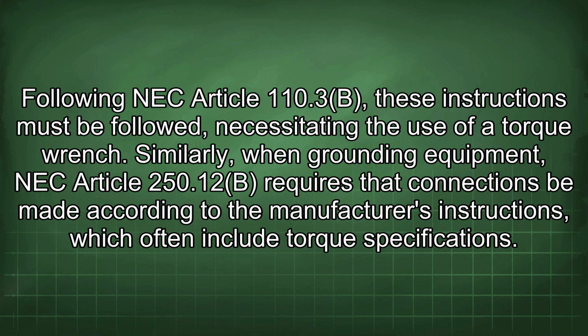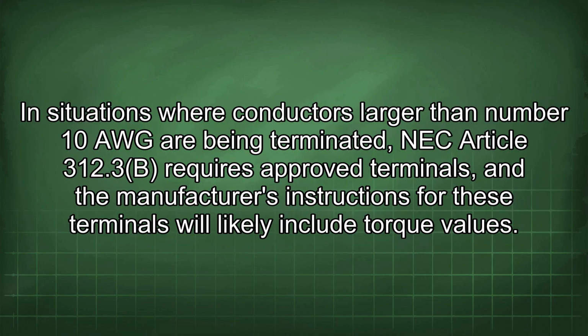Similarly, when grounding equipment, NEC Article 250.12(B) requires that connections be made according to the manufacturer's instructions, which often include torque specifications. In situations where conductors larger than number 10 AWG are being terminated, NEC Article 312.3(B) requires approved terminals, and the manufacturer's instructions for these terminals will likely include torque values.